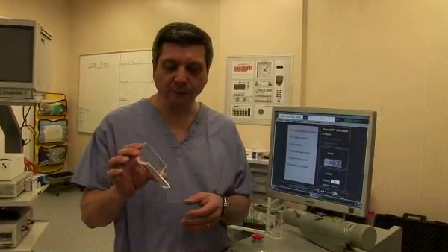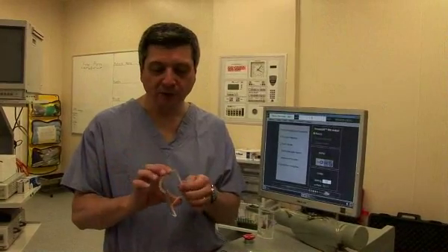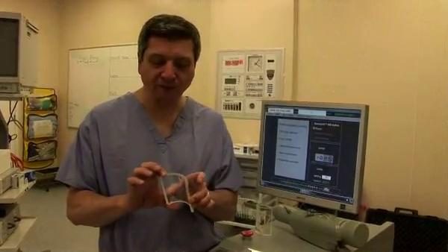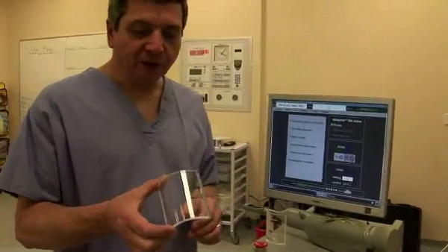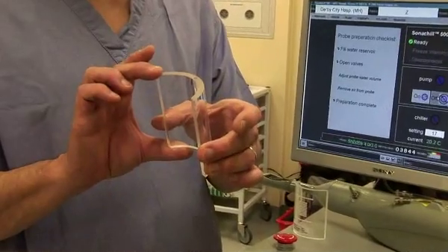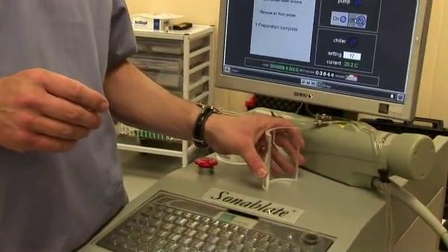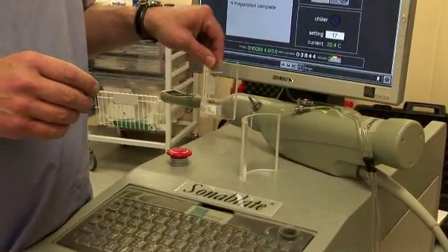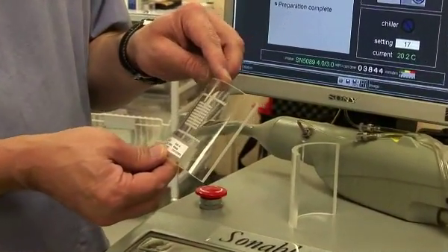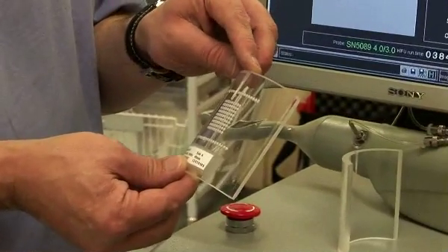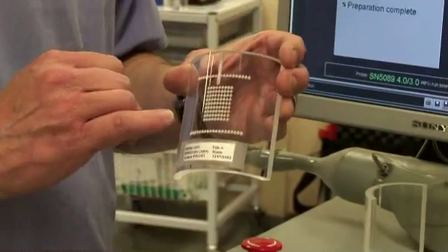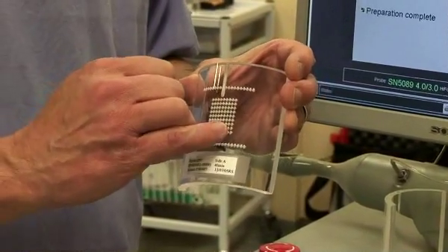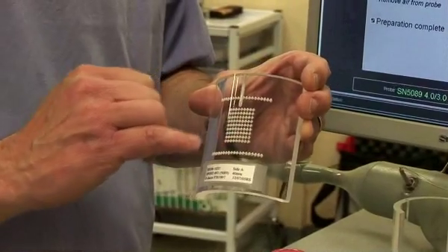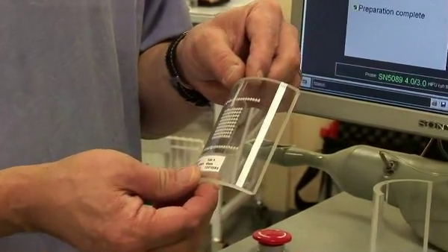In order to ensure the quality of the delivery of the energy, we use perspex blocks which are configured at the same radius that you will find within the rectum. We start off with a plain piece of perspex, and then we immerse the transducer in water and fire the transducer in the way which it would be in tissue. And what we see here is a pattern which has been deposited, that we've chosen, at 1 centimetre centres to ensure the accuracy of the firing pattern throughout the treatment.